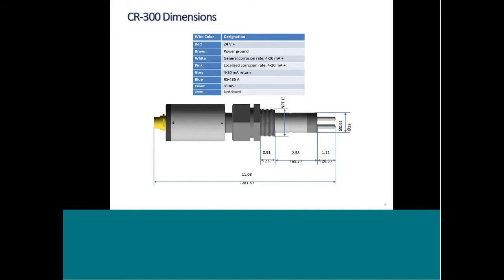So would you install this at the end of your corrosion coupon rack? Would it adapt there? Yes, it could. But remember, if it's a 3/4-inch coupon rack, that diameter or that shaft will not fit into the ID of a 3/4-inch rack. So you would have to make a loop extension on that corner in a 1-inch. And in the manual, we give you a flow installation recommendation. It's typically installed horizontally facing the flow as the flow is coming into the rack. So we actually have a diagram of that in the manual.